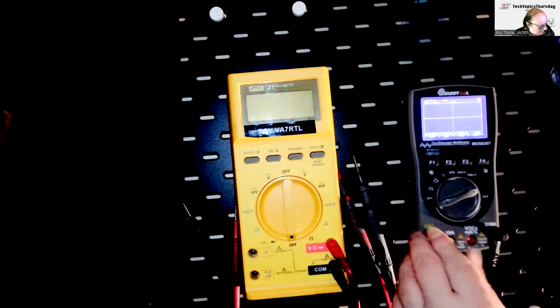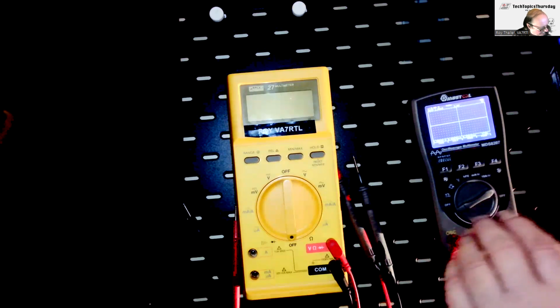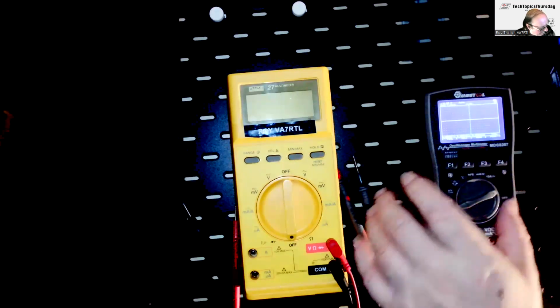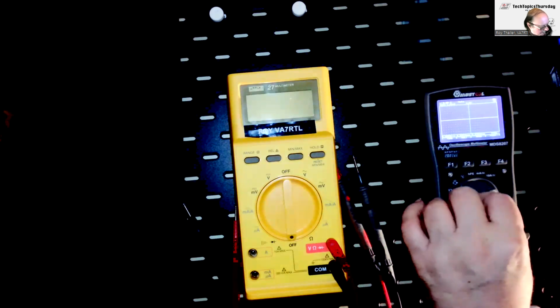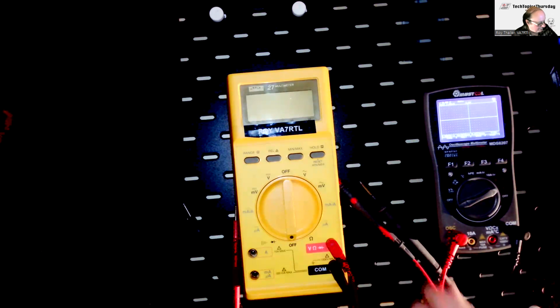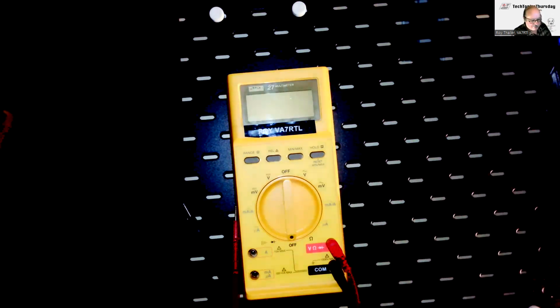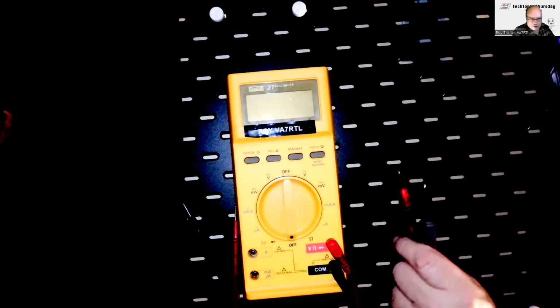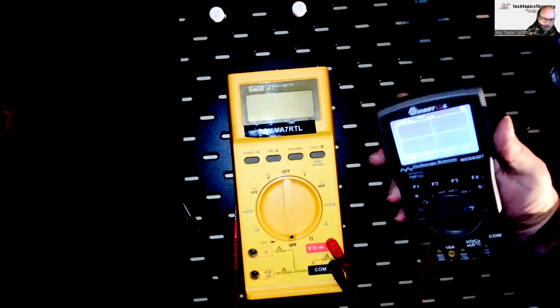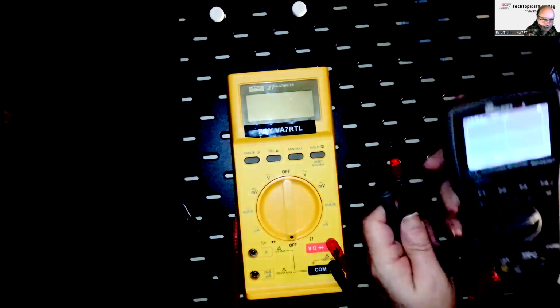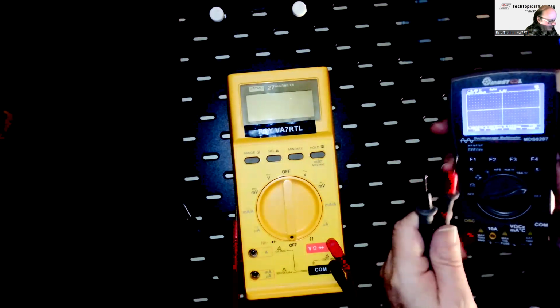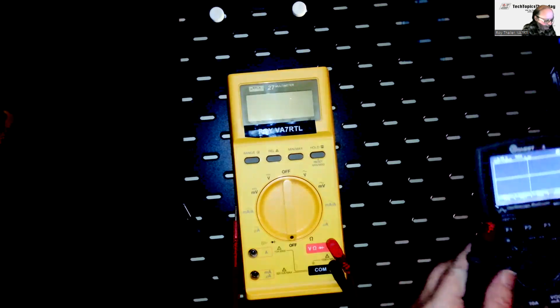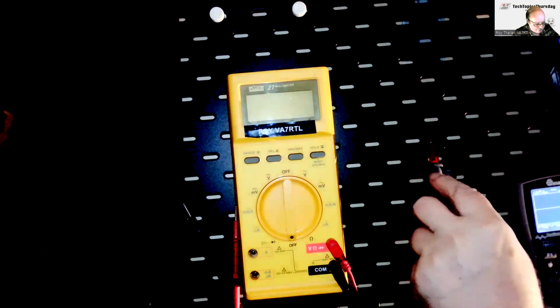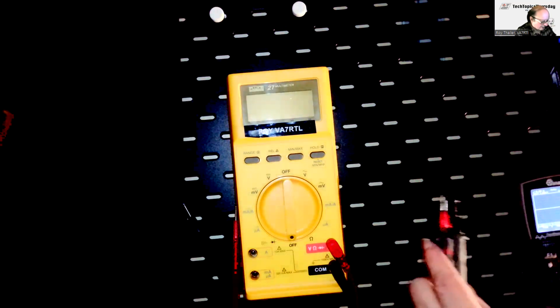I'm not sure if I would trust it on power distribution circuits, but for anything 100, 200 volts it's fine. What you need to do when doing these measurements is decide if you need your Cat 4 meter or your really good Cat 3 meter. If you're holding it in your hand and doing measurements with the probes, you need that good measurement, a good Cat rating, and you want that isolation. But the thing is, you put your meter down and then do your measurements, so if something happens to your meter, you're away from it.